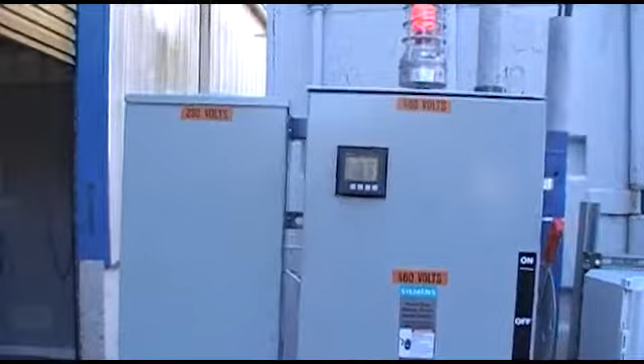The main and most fundamental data for any test are two. First, the very accurate measurement of the used power, which is done by this calibrated watt meter, and that has been re-verified, certified by the manufacturer, controlled by us. Then we have to go on the other side of the reactor to see how we measure the power out.